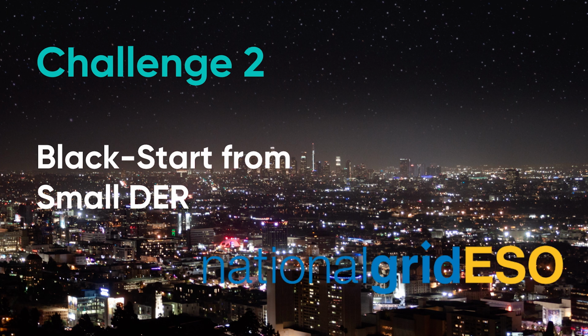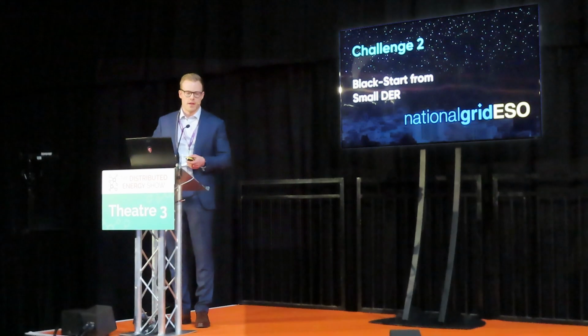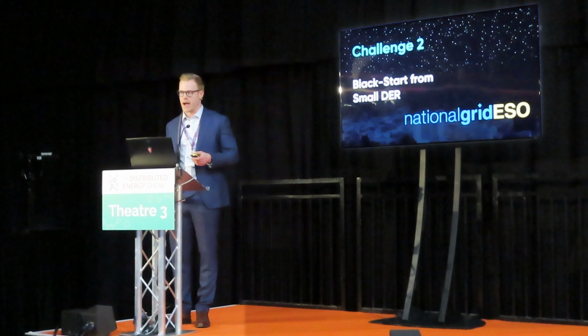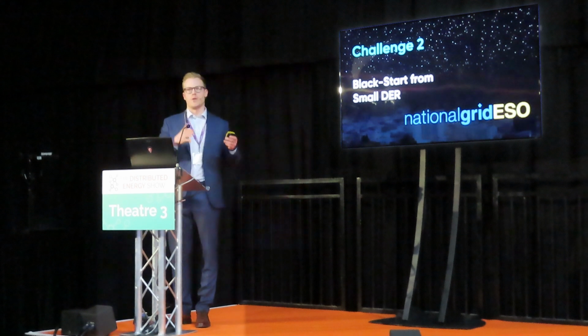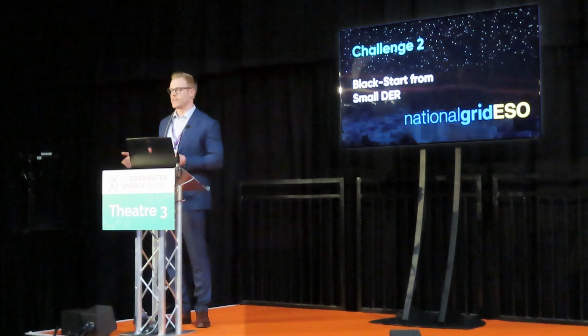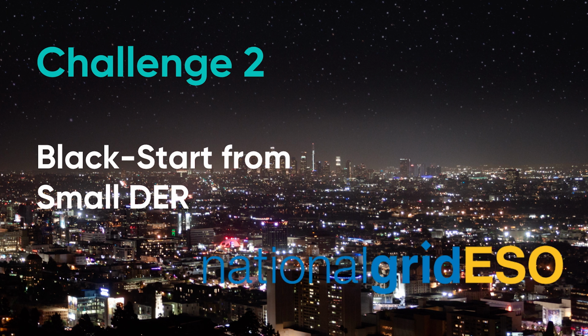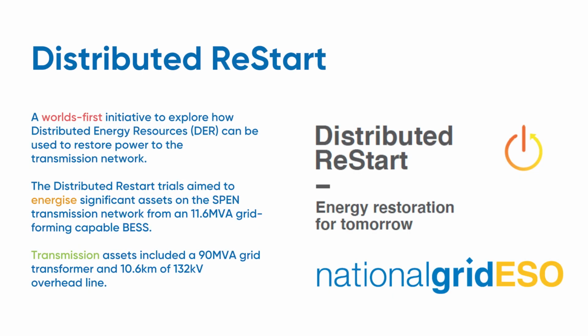Again, traditionally, we would have these large thermal generation assets at the center points of our network. They could power up, and they could become anchor generators, and they could restart the network from these central locations. Now, as we move to renewable generation, we're decommissioning these large assets, and we're moving to many distributed assets all around our network. So we need to find a way to ensure that we can black start our network from these types of assets. This was an initiative we looked at with National Grid and Scottish Power Energy Networks. It's called the Distributed Restart.